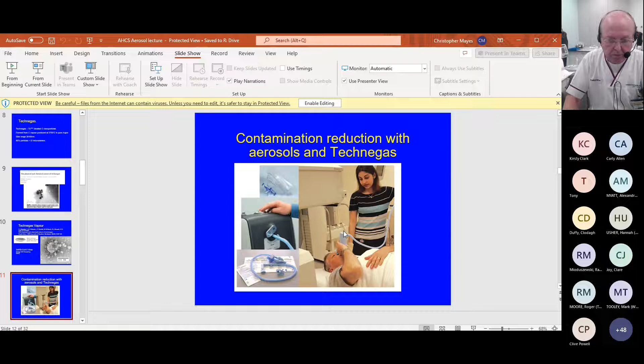Now, it's supposed to be a closed circuit, but I began to realize that it wasn't, because I would do some lung scans in the morning, and then in the afternoon I'd go and do some bone scans, and my bone scans would be contaminated with radioactivity. Two triangles used to appear when I was doing bone scans, which was degrading my bone scan images. So this could only be due to the fact that some of that technetium-99 Technegas, that vapor, that aerosol, was escaping into the atmosphere and then getting sucked into the back of the gamma camera.